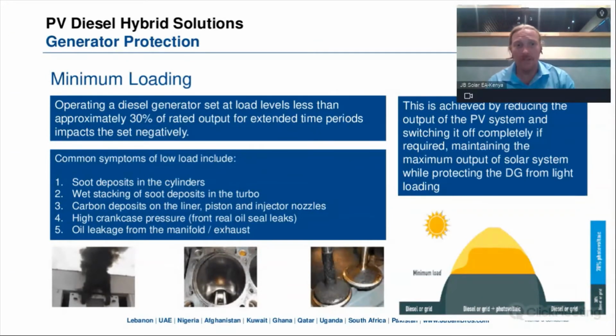Okay, so minimum loading. This is because diesel generators are not built to operate below approximately 30% of their rated capacity. So whatever the rated capacity of the diesel generator is, it should not be run below 30% of that number. And the reason is there on the bottom left. Those are some of the issues that will happen if you operate your diesel generator below the minimum rated capacity. You'll get soot in the cylinders, you'll get wet stacking of the soot deposits in the turbo, carbon deposits on the liner, piston, injector nozzles, you'll get high crankcase pressure, you'll get oil leakage in the manifold and the exhaust.